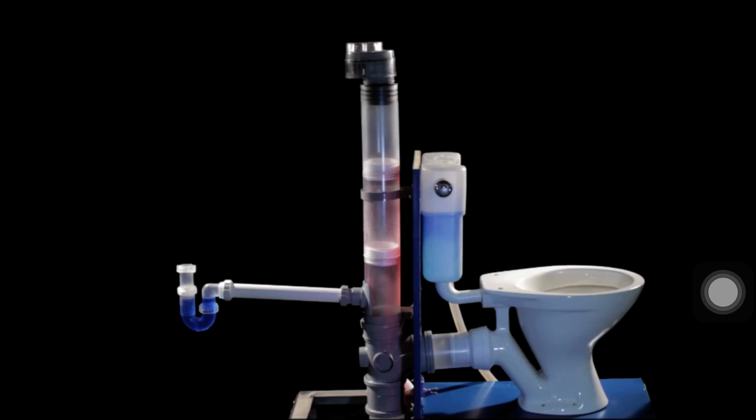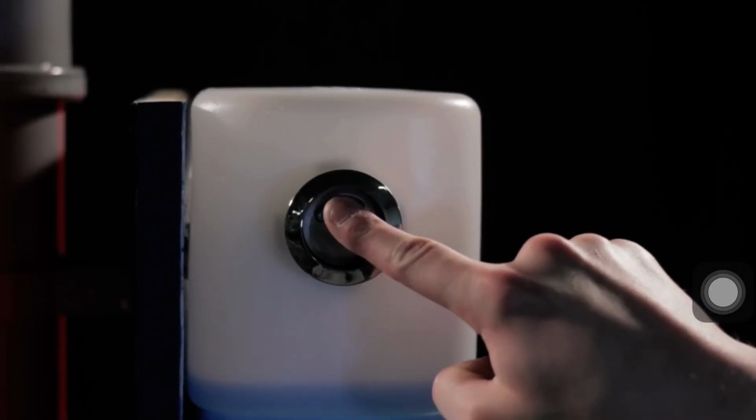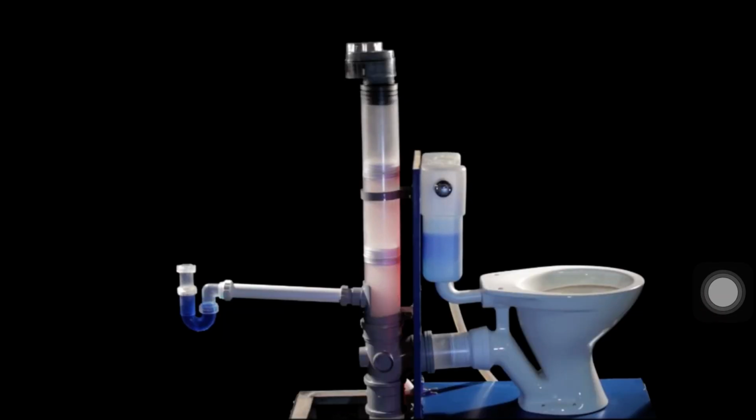Under positive pressure or neutral pressures, it remains airtight, keeping sewer gas within the system. It is much easier to move air than water, so during negative pressure, it allows air to be drawn in. This ensures water seals are maintained. When the pressures equalise, the valve closes again.